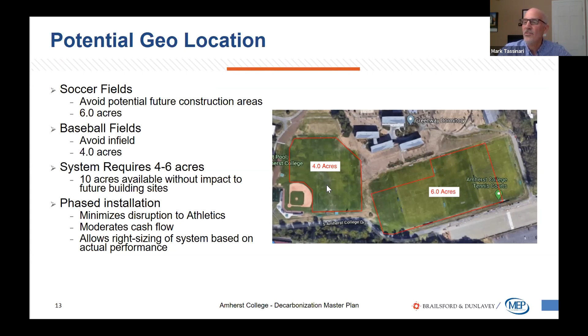A key point about the geo exchange field is that it will be developed in phases, which gives us a couple of advantages. First, it allows us to mitigate the impact to athletics by taking off just one, or at most two, fields at a time. It also gives us the opportunity to gather empirical data on how the initial field is performing in the first phase, which can inform subsequent phases and help right-size them.